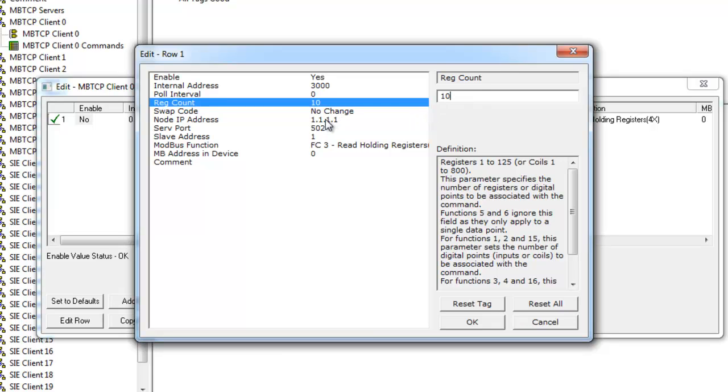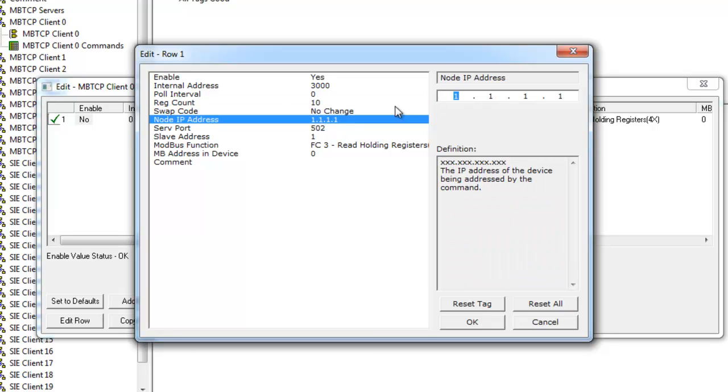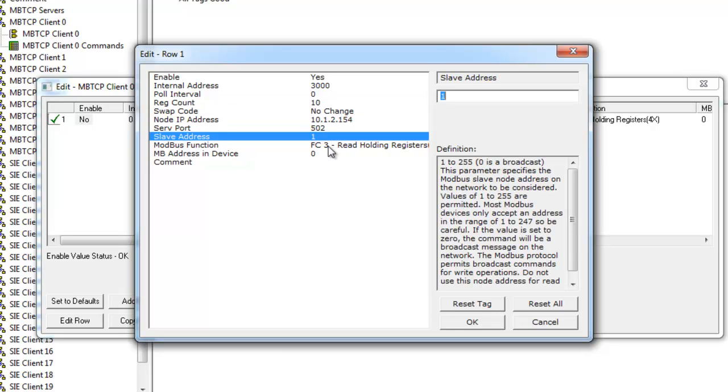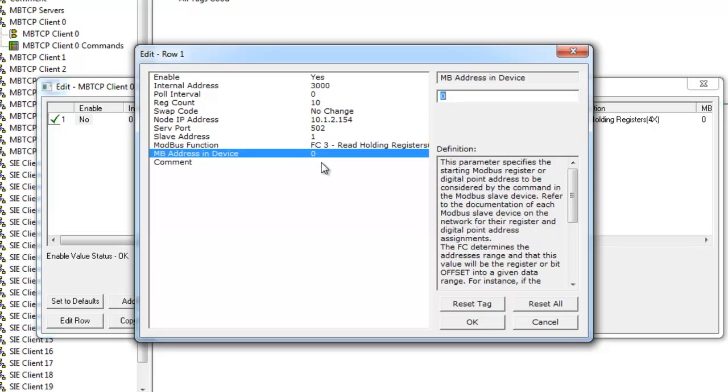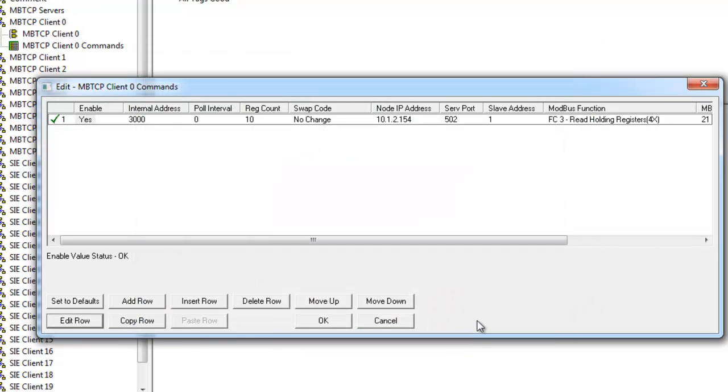The destination IP address that we're going to read from is 10.1.2.154. Slave ID we'll leave that as 1. Function code 3 read holding registers. We're going to read from the address of 21 in the target device. Click OK, and that's it for that command.